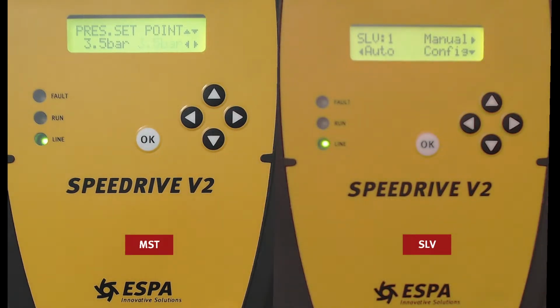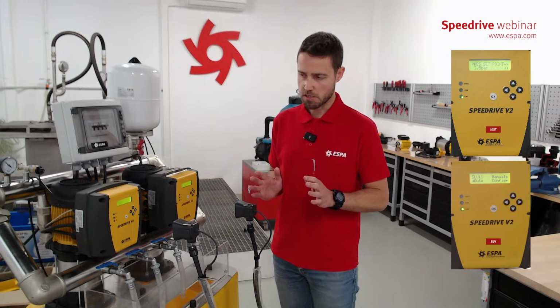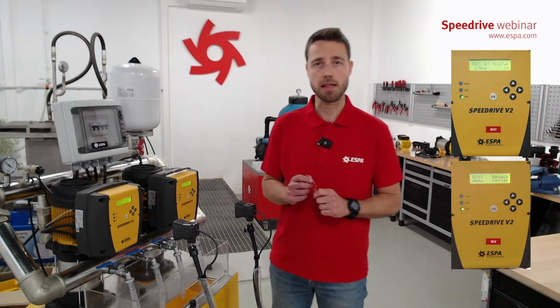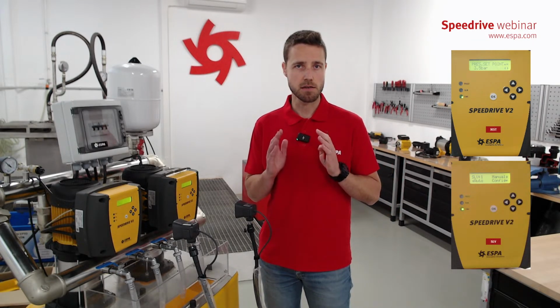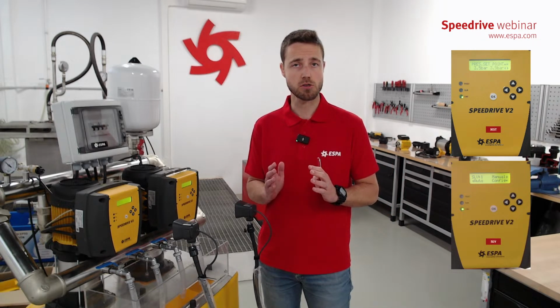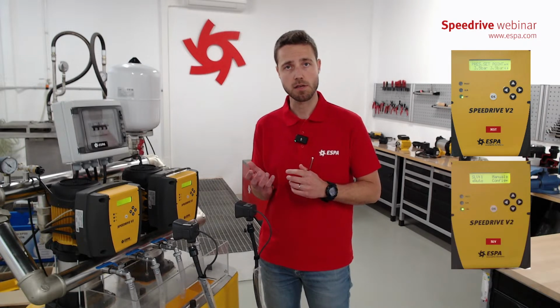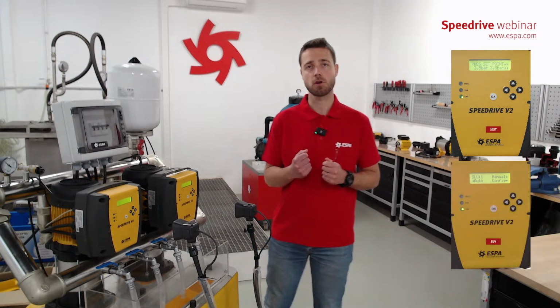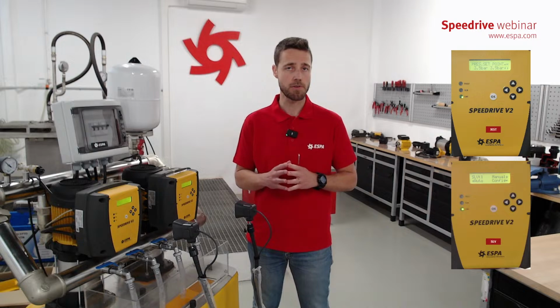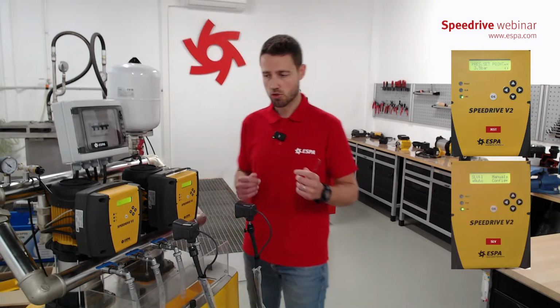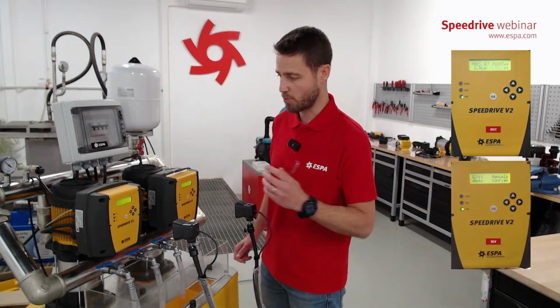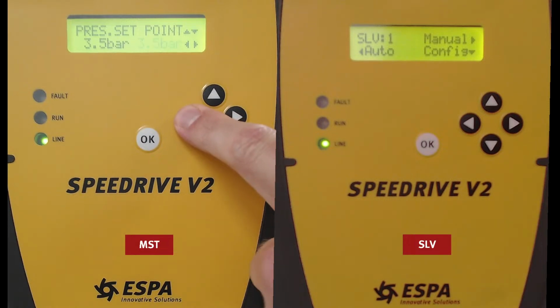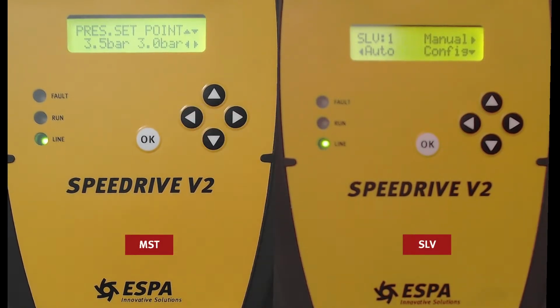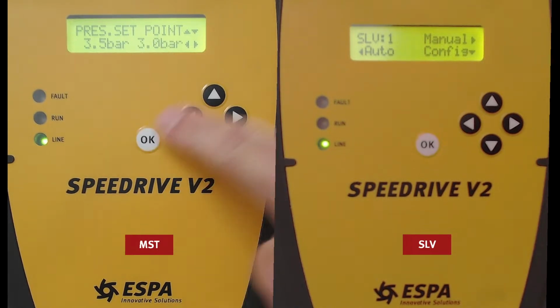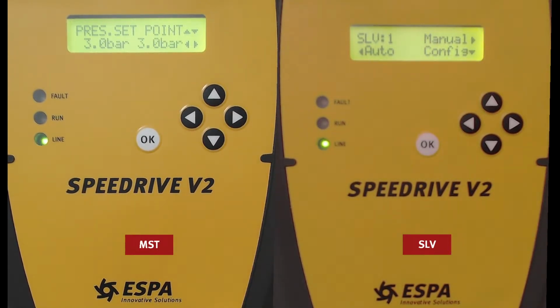Set point. This is normally the only thing that we have to configure in a simple startup, because our speed drives come from factory already configured or set up. So we adjust the desired pressure. For example, in this case, we can go and decrease it to 3 bar. We press OK in order to save it.